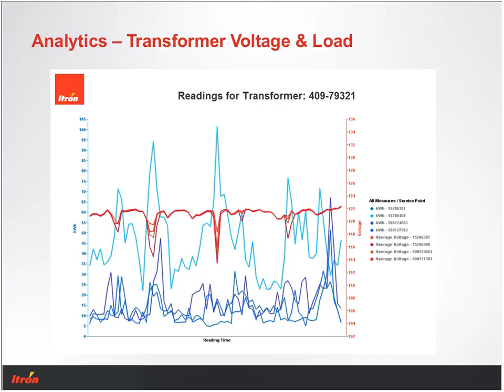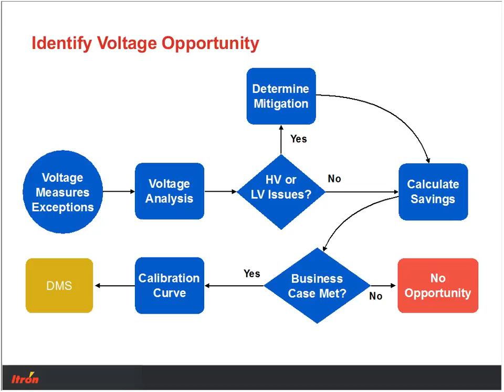So once again, here's how we walk through that. What we just did with the analytics is we took a look at those voltage measures and exceptions. We did the voltage analysis to understand where those low and high events were. We determined whether they were or weren't a real issue, and then we determined if there was a mitigation path. Calculated our savings. You didn't see that part, but we would calculate the savings, apply it to the business case, and determine if we could or could not lower the voltage, and if so, calibrate our curve based on those voltages.